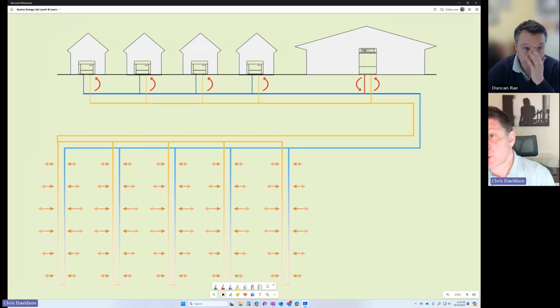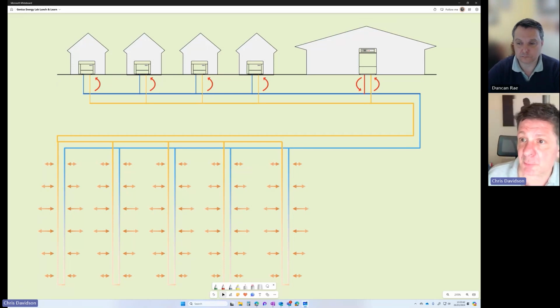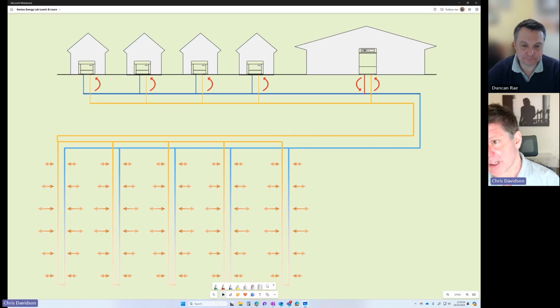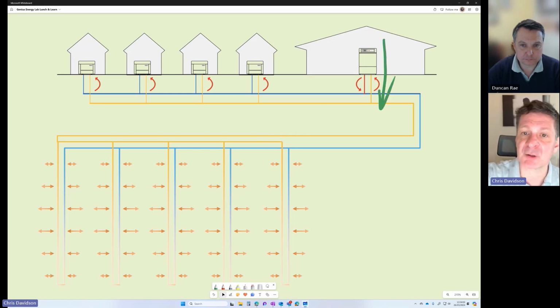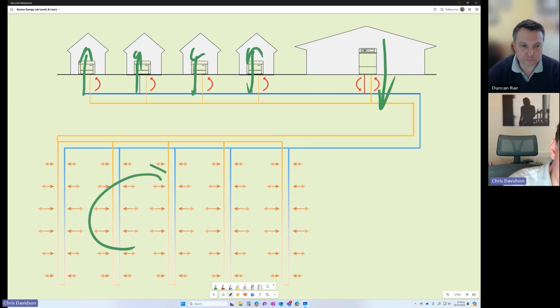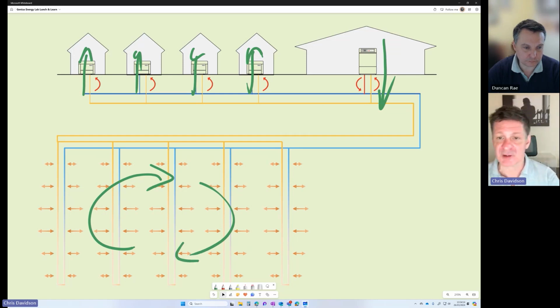Now if you go along to a supermarket and say you're a lovely source of heat, supermarket, would you like to recycle that heat and put it into houses being built alongside, they'll probably see that as risk and too much hassle, and won't be particularly interested. But with this new heat zoning legislation, we might be able to go along to that supermarket, reduce their cooling costs - and it can be a dramatic reduction in cooling costs - and inject heat into that ground loop. Then take that heat out into those dwellings or office buildings, whatever. Again, we're extending that heat recovery interseasonally, which is the real magic of ground source.